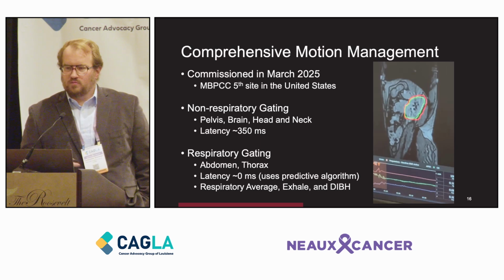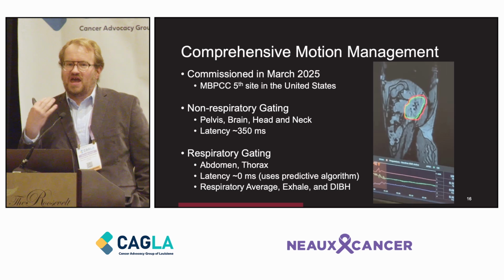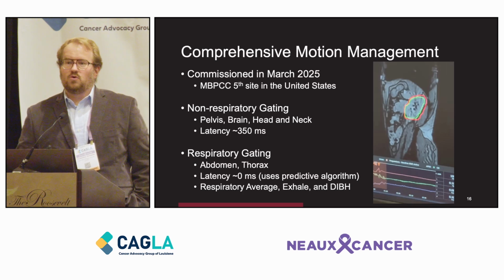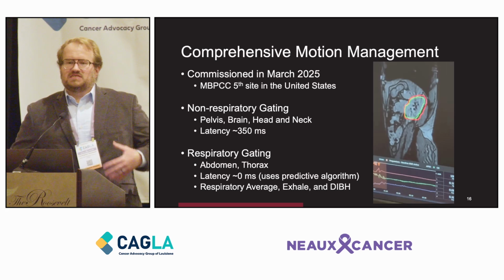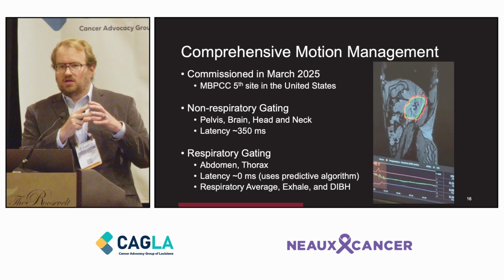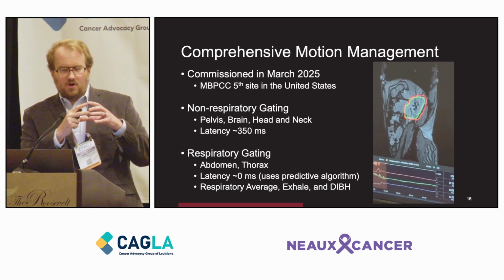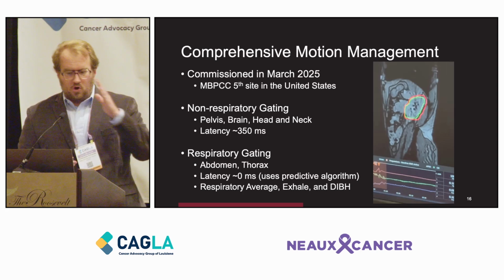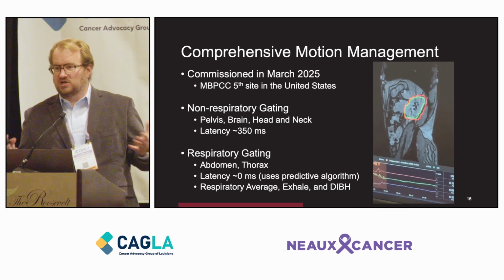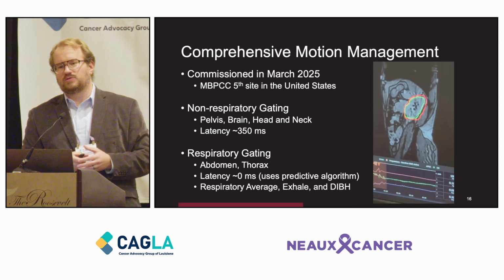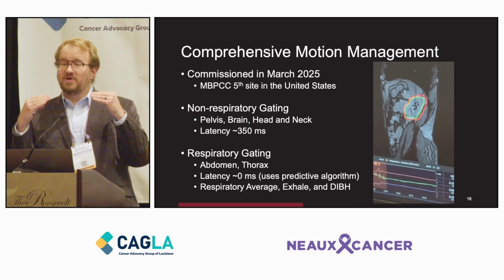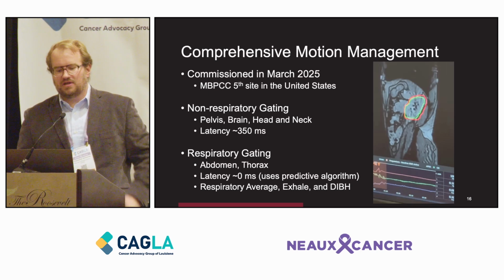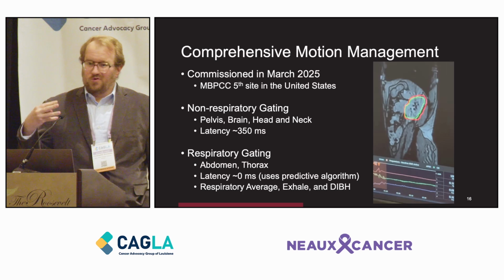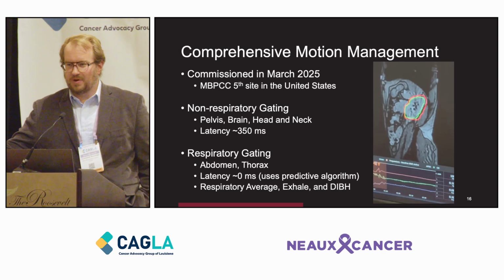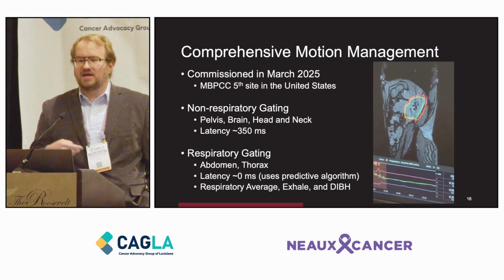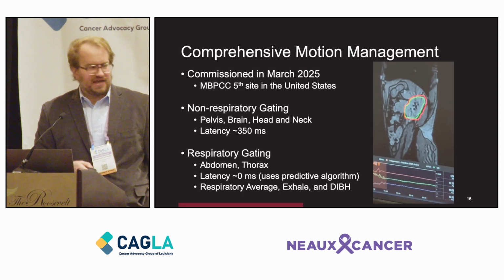Breath hold gating is another, perhaps one of the ones that's simpler to understand. If we can have our patient hold their breath while we're imaging them, and then hold their breath during treatment, for sites in the abdomen or thorax, we can basically remove all respiratory motion. On the Unity, by tracking the target, it works very similarly to the non-respiratory gating. This is the strategy we would employ if we expect to see motion, but we want the patient to hold their breath to stop that motion while the beam is on. Typically, this is going to require the patient to hold their breath for 20 or so seconds at a time for multiple repetitions in order to get through a full treatment. But for patients who are otherwise healthy and have good performance status, it is an option.